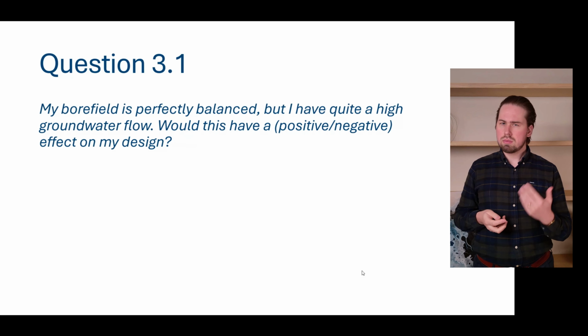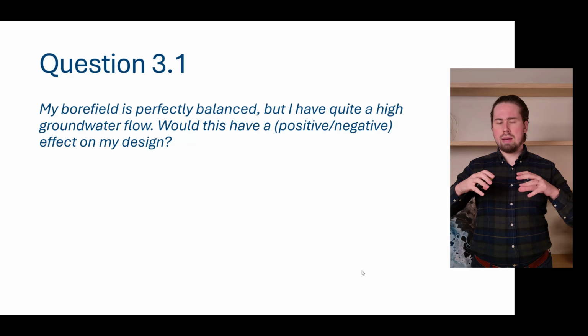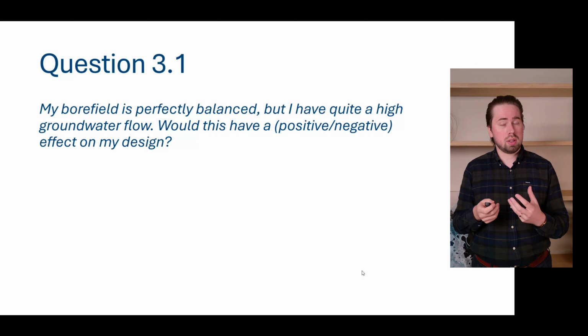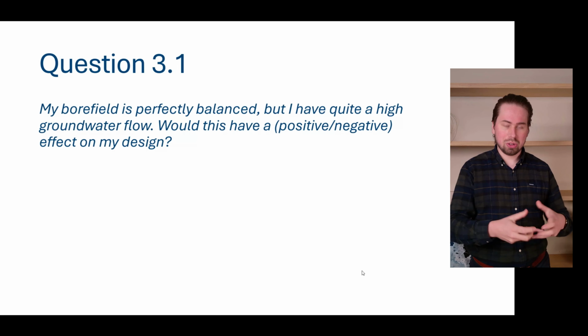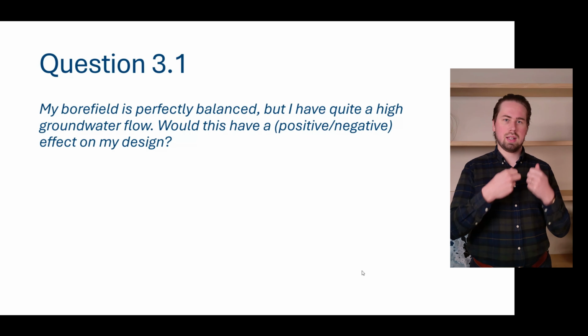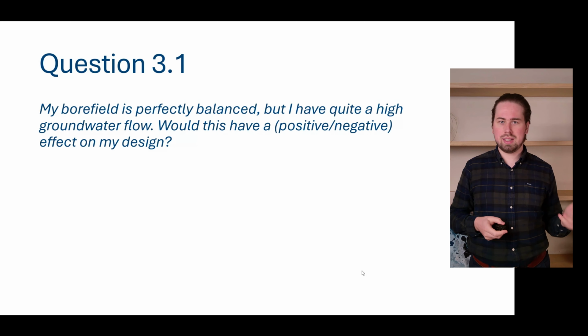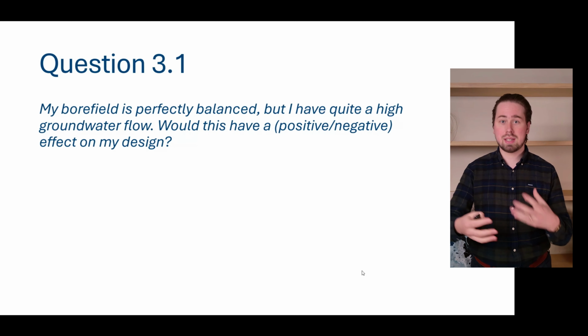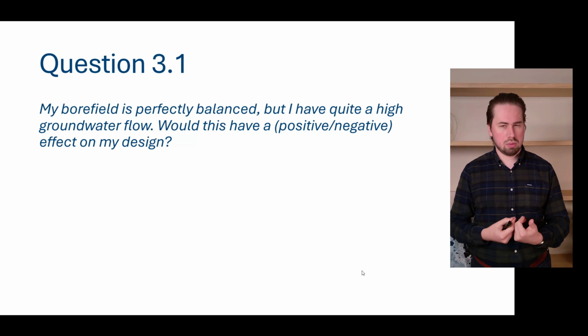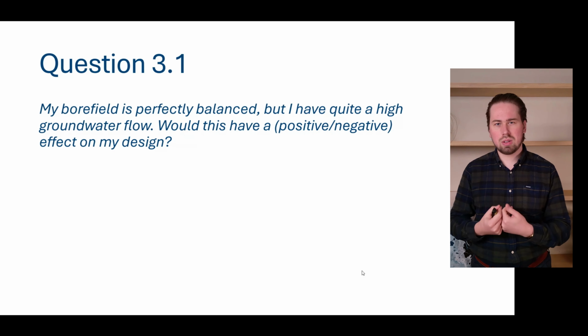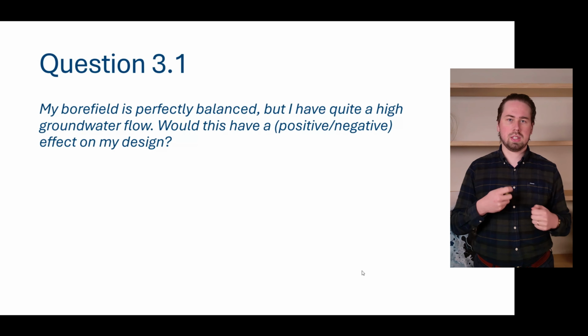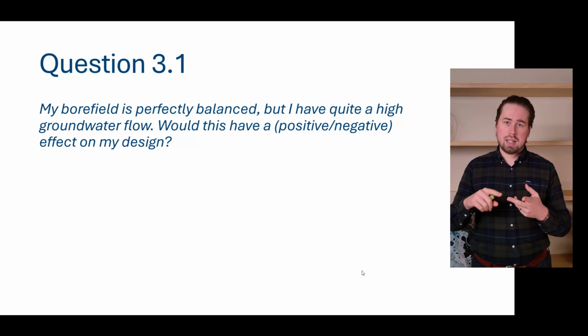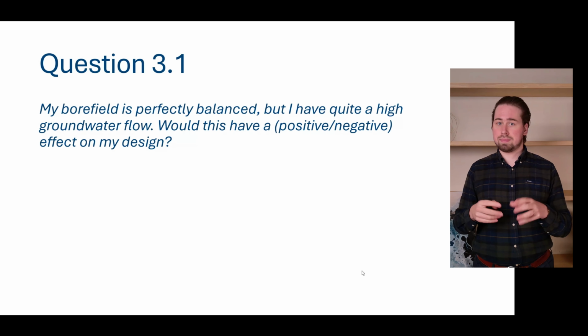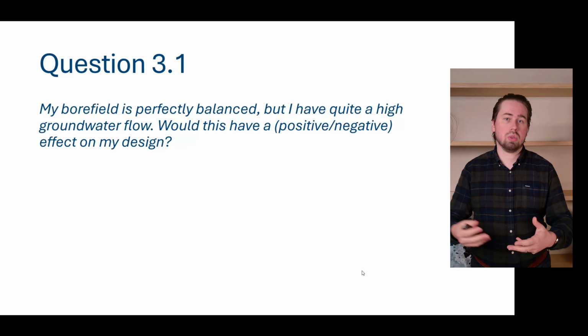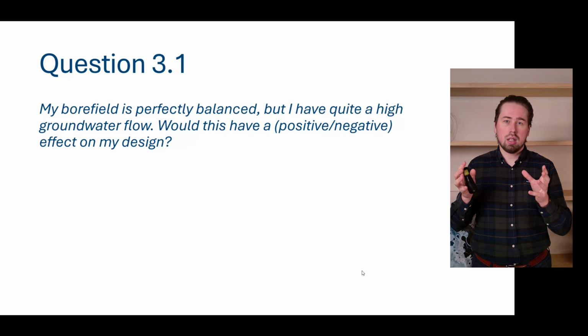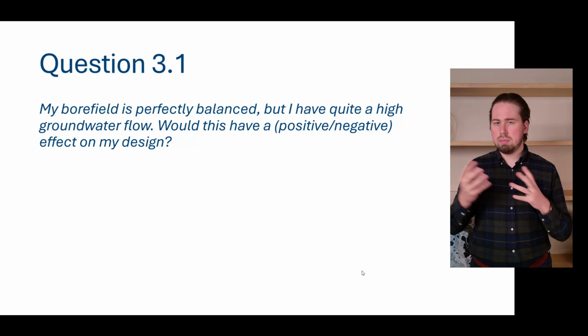For example, and we'll come back to that in a later question, if we have a really high cooling need in our building, we really want our stored cold from winter. We need that in order to make sure that we can deliver the cooling to the building. But if our groundwater takes that away, perhaps we need an extra borehole to compensate for that and still make sure that we can deliver the cooling to the building. So yes, it can also have a negative effect when our bore field is perfectly balanced, both on the design aspects, but also on the efficiency of your total system, because part of the energy that's stored goes away. So your total seasonal storage efficiency goes down. So that's a little bit the nuance there.